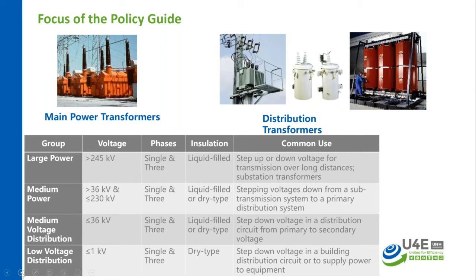These transformers can be used for generation, particularly at the new solar and wind power plants which are coming in. And this transformer also can be supplying electricity to customers, such as residential, commercial, and industrial customers, etc. The policy guidebook also includes the dry type transformer. These dry type transformers are generally air-cooled transformers installed in densely populated buildings, addressing issues related to leakages and other issues such as fire, etc. So this document includes these two types of transformer commonly used in the distribution network.